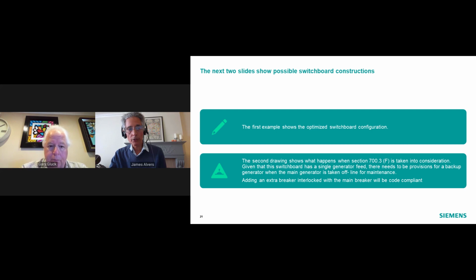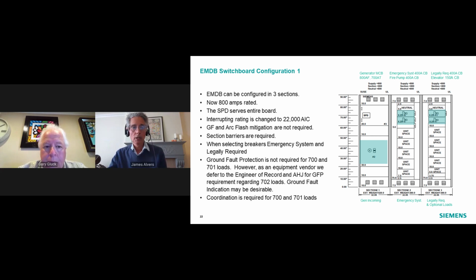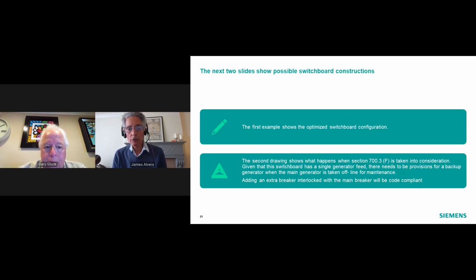So now I'm going to show some possible switchboard constructions. The first example is the optimized switchboard based on the one line. The second drawing shows what happens when section 700.3F is taken into consideration. Given that this switchboard has a single generator feed, there needs to be a provision for a backup generator when the main generator is taken offline for maintenance. So adding an extra breaker interlocked with the main generator breaker would be code compliant.